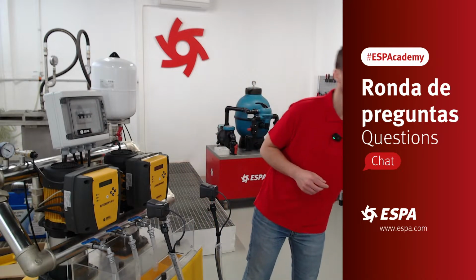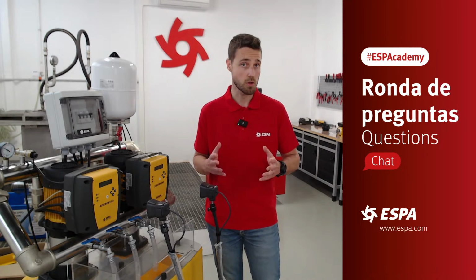And the second one, the USB only for update. Yes, for us and for the users, the USB only serves for updating the firmware. We don't give other use right now to the USB connector. Something else? No? So, okay, another colleague asked us which is the minimum diameter of the pipe suction. So the minimum diameter is the one calculated in order not to go over this 1.5 meters per second in the suction. So the speed of the flow doesn't have to be too high in order to work properly.